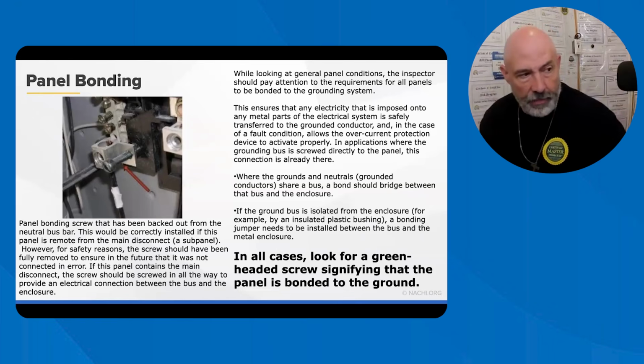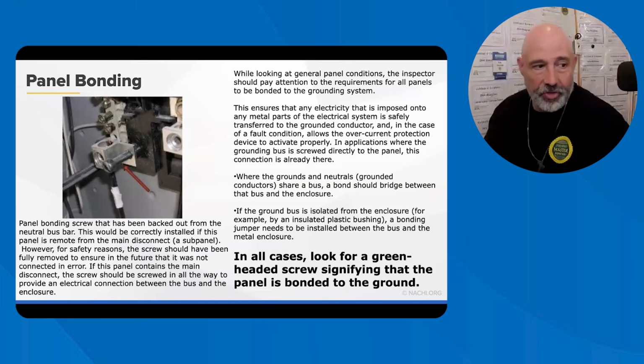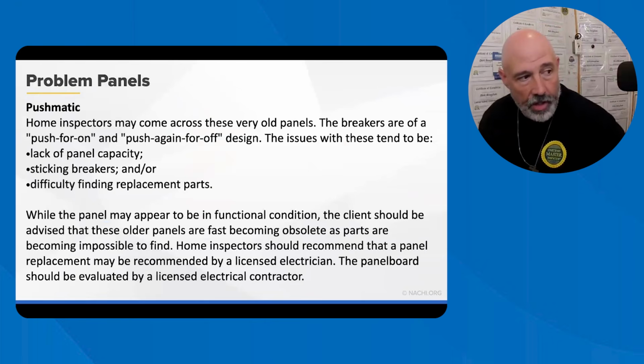If the panel board screw is there and it's in a sub panel, you want to make sure that you point that out to them that, hey, there's a grounding screw there. It should be taken out personally. But in all cases, look for the green headed screw if it is in a regular main breaker panel.